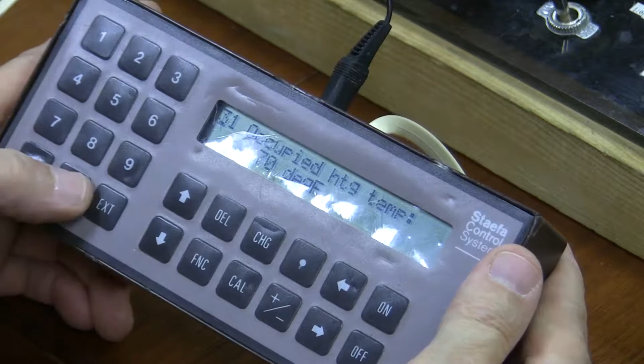Because if somebody's not happy, the first thing I should say to myself is, let's plug in and actually see if it's controlling to the temperature that we want. If we need to, we could lower the set point. Now, of course, the easiest way to lower the set point is just to turn the knob down, right? But you may have a thermostat that doesn't have a set point, in which case you could go here and scroll down to set points. You could hit enter, and then you could change the set points. However, as soon as you disconnect, whatever was in the main computer back at headquarters will write back down over the top of it. So you really have to go to the graphics to change the set point. But that's really simple and easy, and you all know how to do that, hopefully, as well, right?